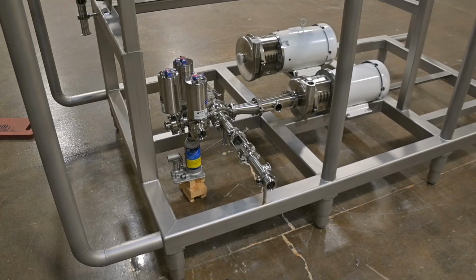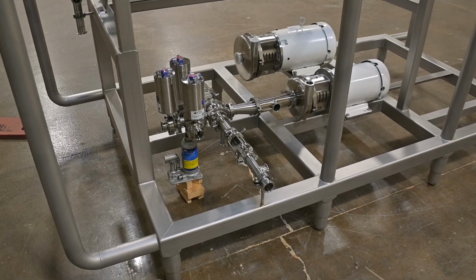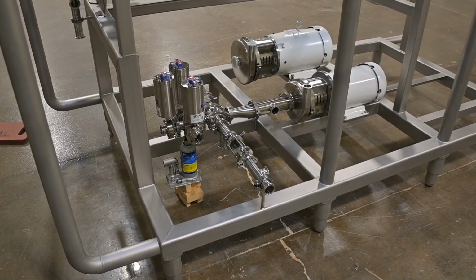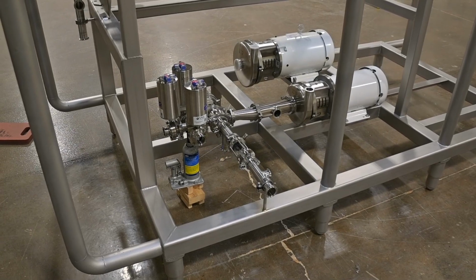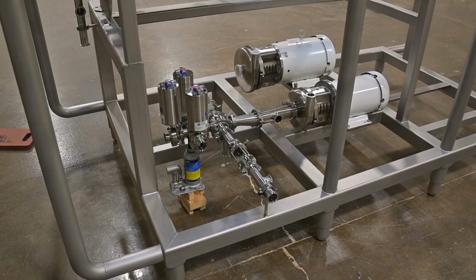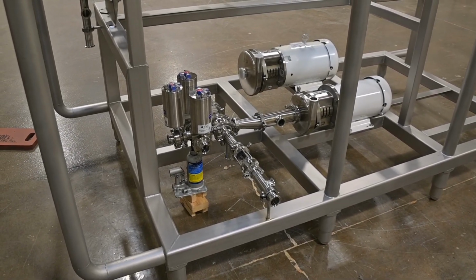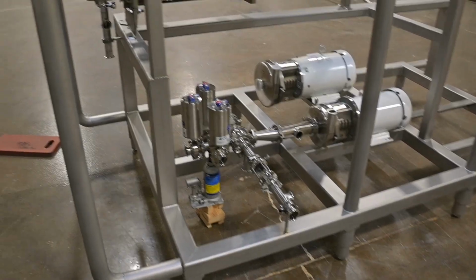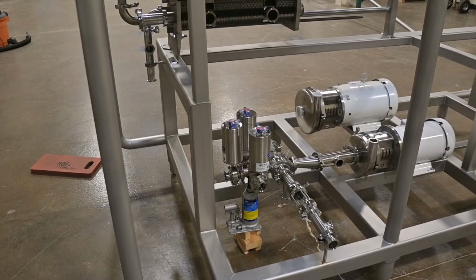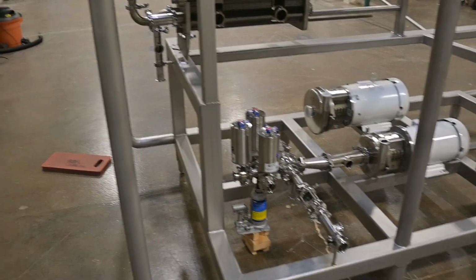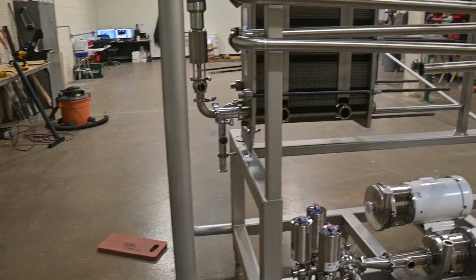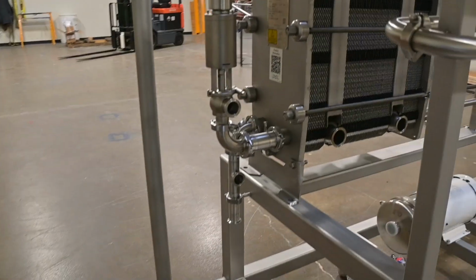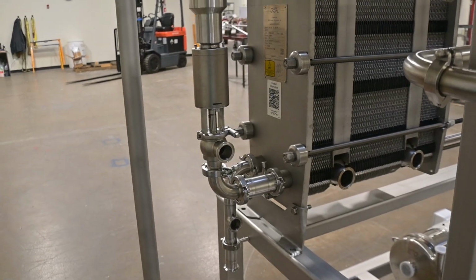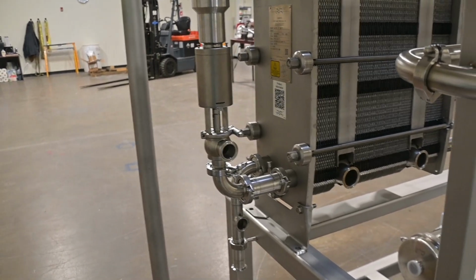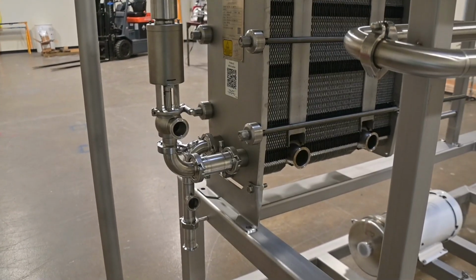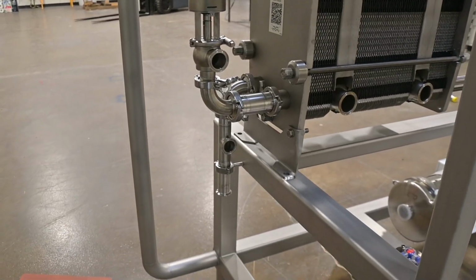The product input section is in now, and I like to pitch it down about a degree so any product rolls back out of there when the machine's not in use, so nothing gets trapped in there. Then it has to be tied in over here, this valve assembly up to some more valving, which is going to be part of the output section. So input and output tie together, and it exits out over here through another valve that's not in here yet. I got some of the glycol stuff in over here now.